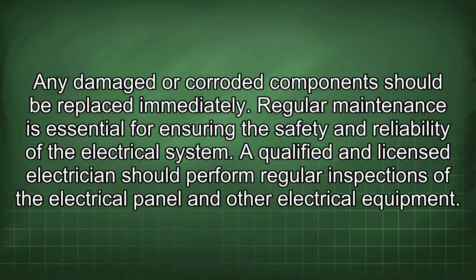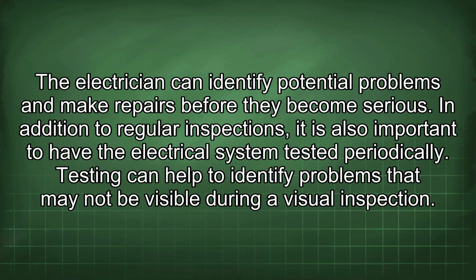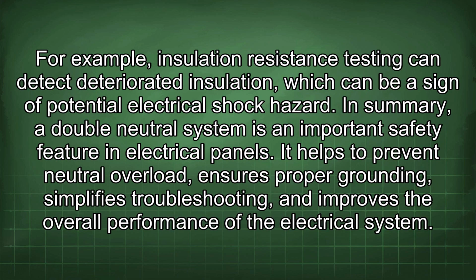A qualified and licensed electrician should perform regular inspections of the electrical panel and other electrical equipment. The electrician can identify potential problems and make repairs before they become serious. In addition to regular inspections, it is also important to have the electrical system tested periodically. Testing can help to identify problems that may not be visible during a visual inspection. For example, insulation resistance testing can detect deteriorated insulation, which can be a sign of potential electrical shock hazard.